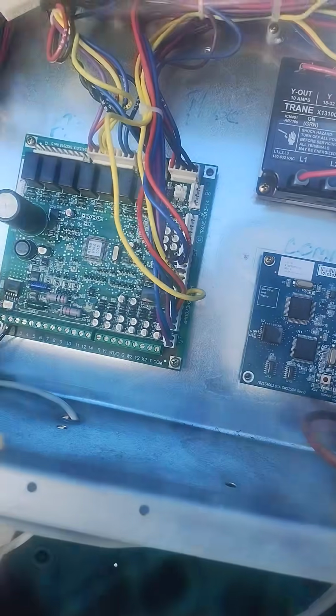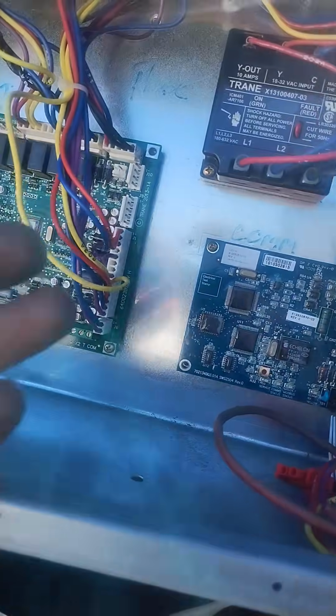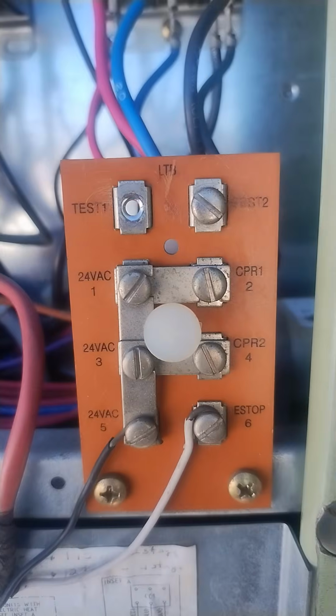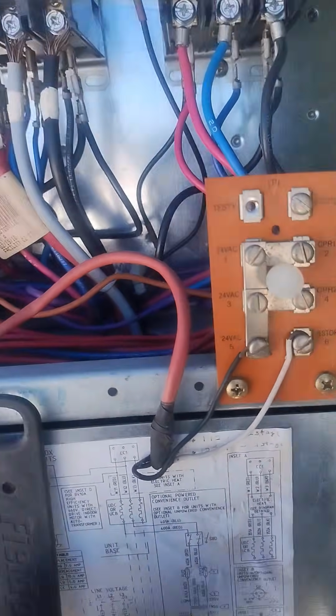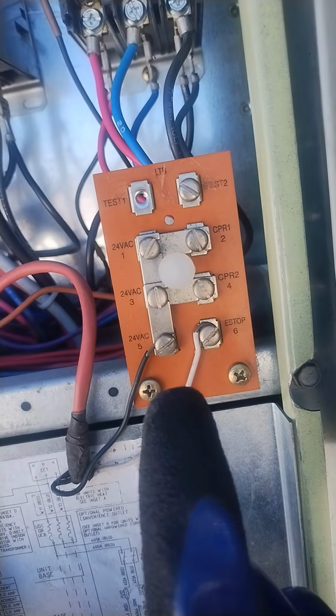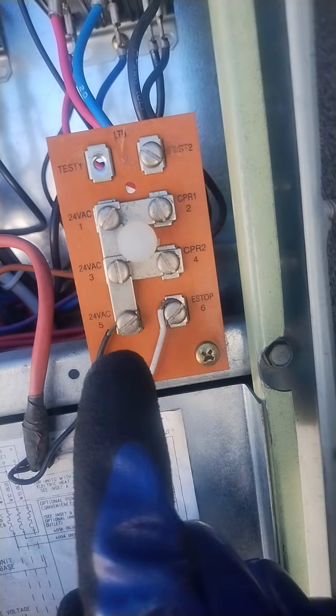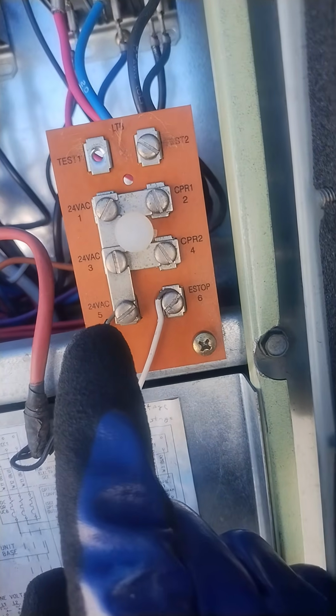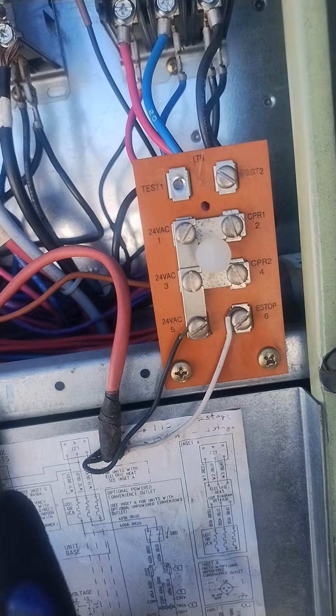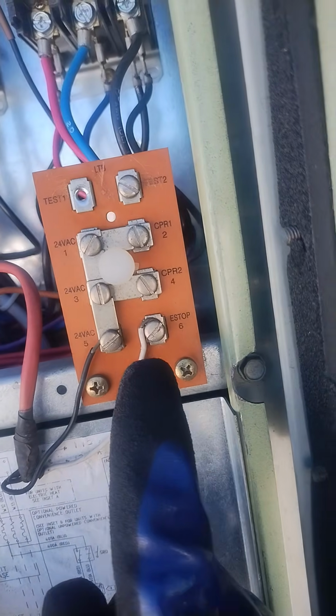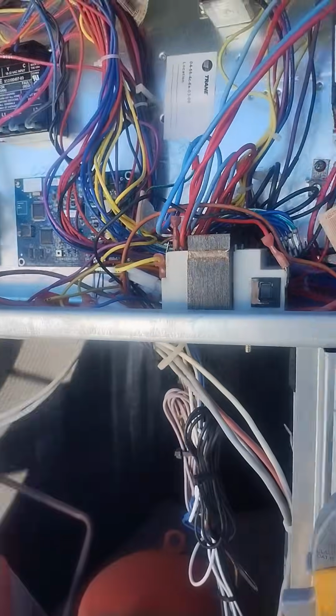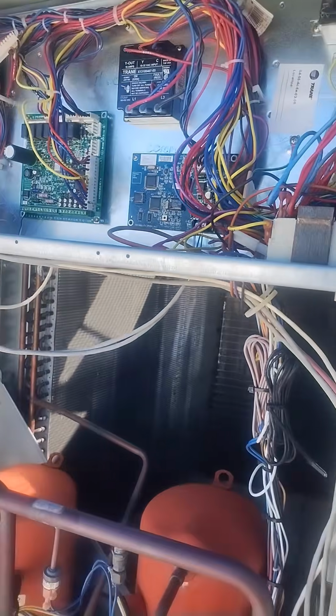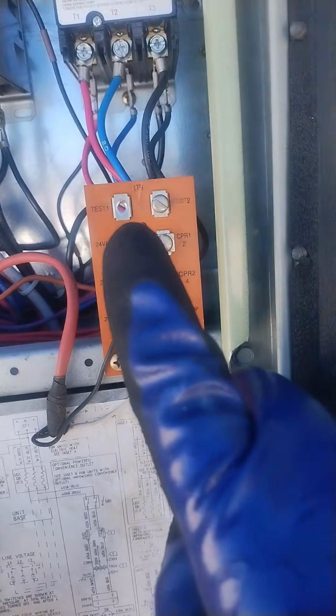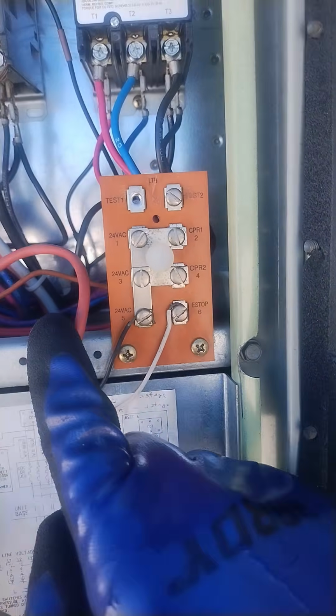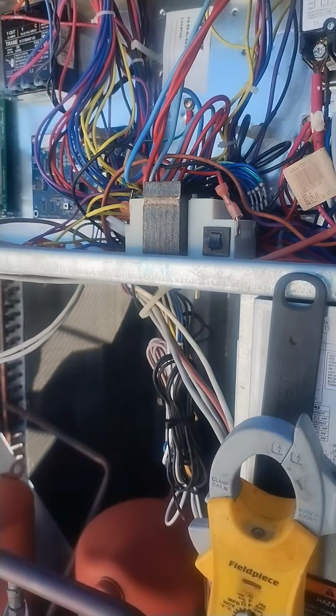And most of the time, 24 volts is what lights these little LEDs on these boards and everything like that. So the next thing I did was I came over here. Should have been 24 volts on these test pins. There was no 24 volts. Should have been 24 volts on this fire alarm system, because the 24 volts goes down to the fire alarm system. If everything is good on the fire alarm, it comes back up on here, and then it lets the unit continue to do what it does. So I didn't have 24 volts on my test terminals. I didn't have 24 volts on my fire alarm system interlock.